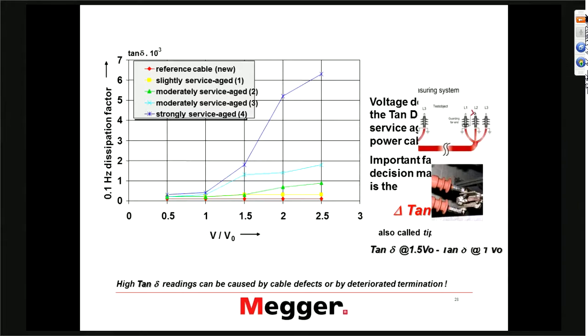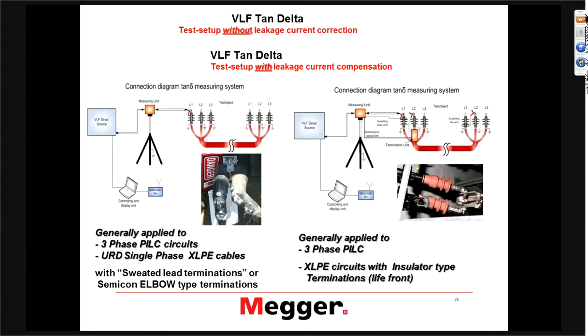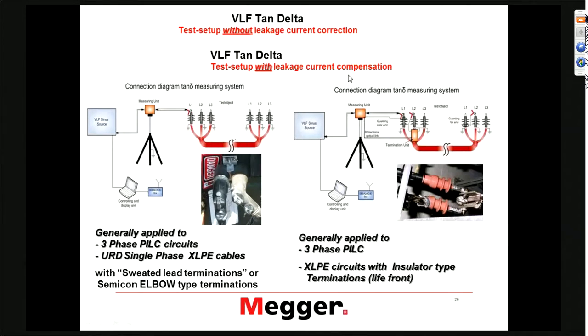When you do Tan Delta testing, it can be done in various ways — you can have external or internal Tan Delta equipment. Typically, most equipment today goes clearly towards the internal because it's a whole lot easier in the field to apply. Only if you would really require very high precision type measurements, where you also have to look at the leakage current over the terminations, is there a more involved method — essentially using guard rings in the field. For the typical measurement, this is not required, and we're typically not needing that type of precision measurement.